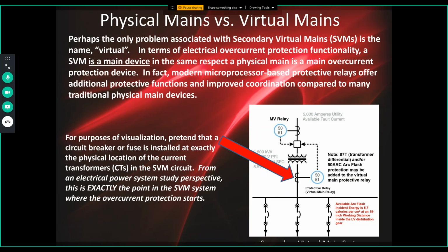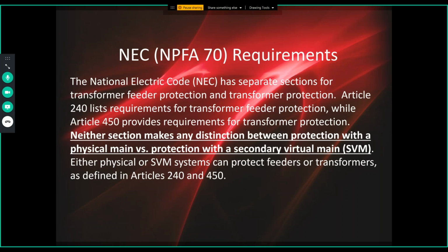A medium voltage device, such as shown in the primary breaker here. So in terms of NFPA 70, National Electric Code requirements, there are separate overcurrent protection requirements in Article 240. And for transformer feeder protection, well, Article 450 covers the transformers. So we've got standard overcurrent for transformer feeders in 240 and then transformer protection in 450.